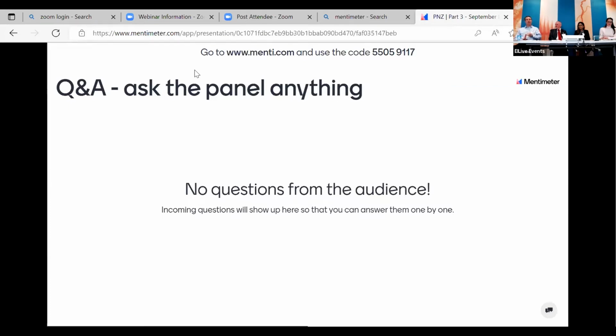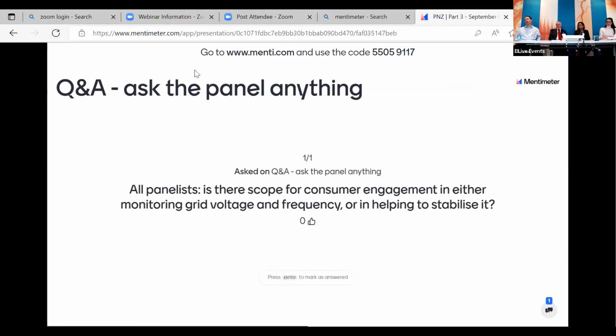Kind of dynamic volts - what that means is under fault, the volts drop during the fault for a sudden millisecond. And if the voltage isn't sufficient, as Tim alluded to, what then happens is other things connected to the system struggle to inject power. And that's a real issue because you've got a fault over here that subsequently cascades to other things because they're struggling to see the voltage and inject the power.